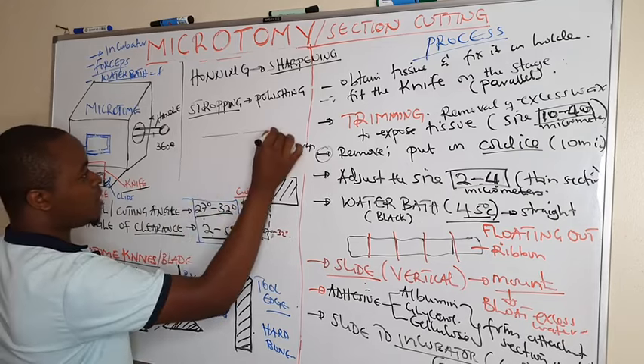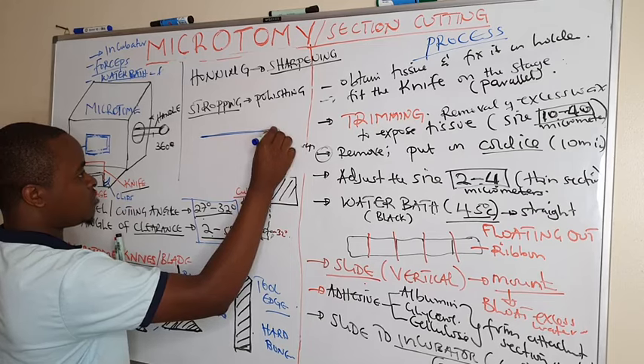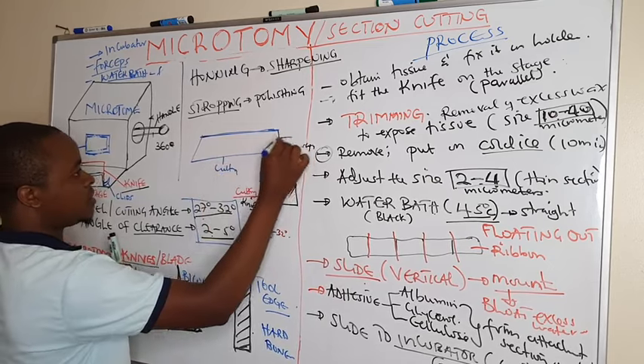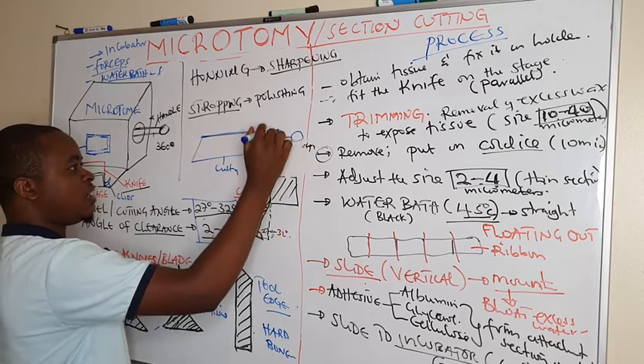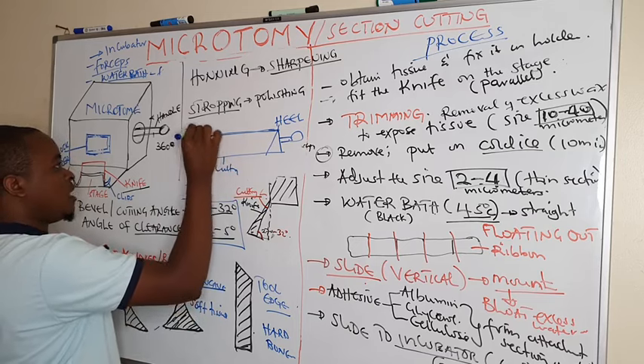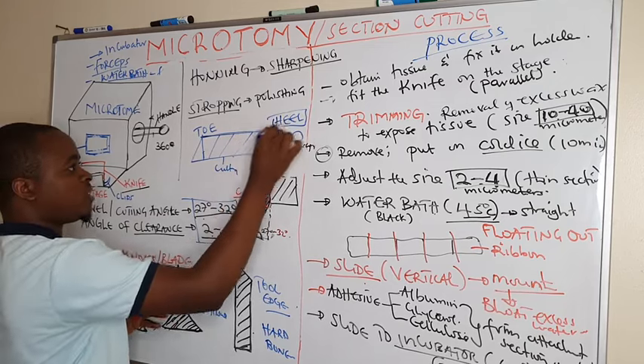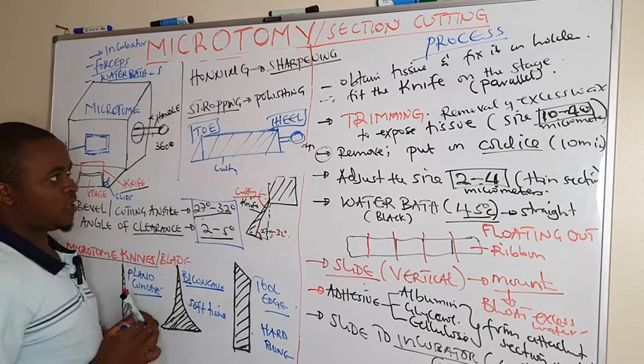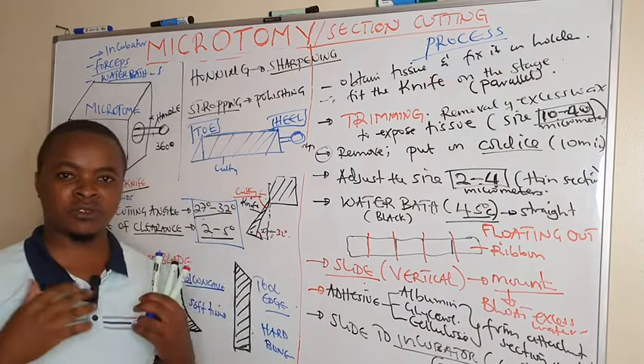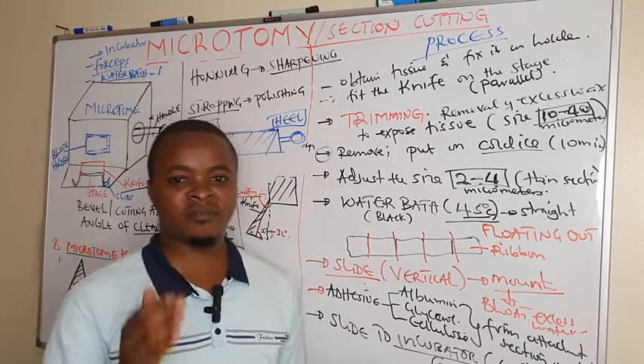Finally, on the microtome knife: the angle formed near the handle is known as the heel, and the angle formed away from the handle is known as the toe. When the knife becomes blunt or has niches, we can always hone using different honing stones. Thank you so much for learning with us.